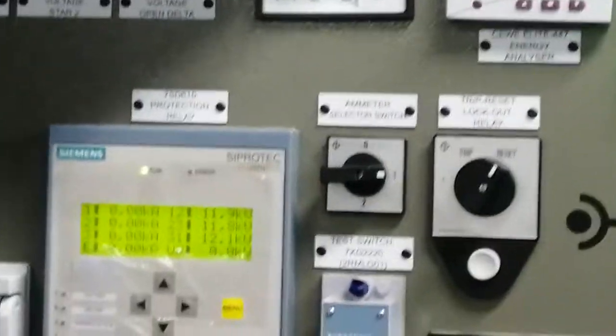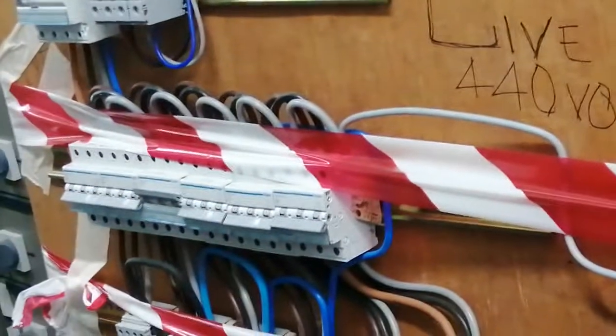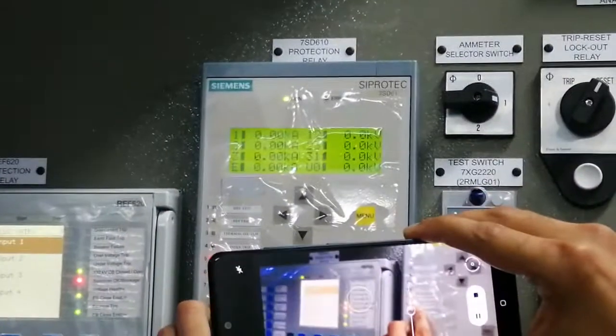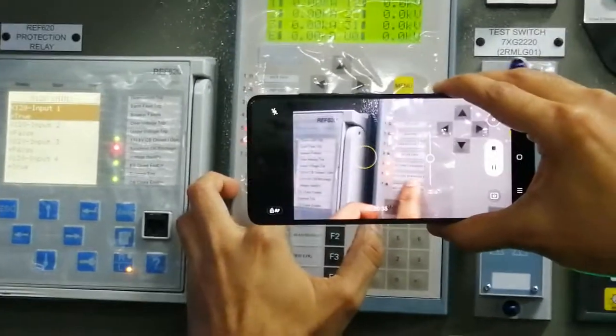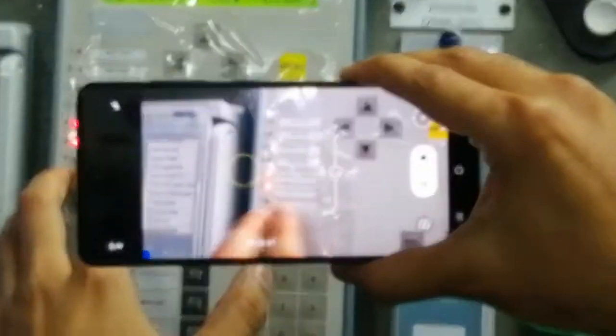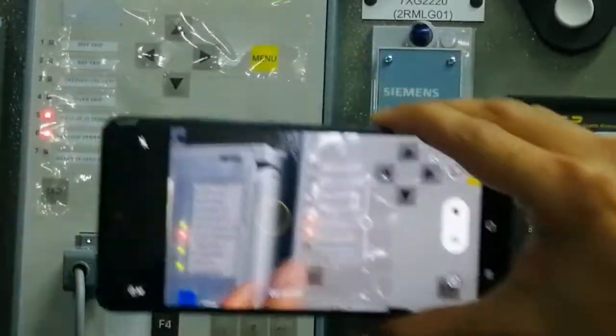So first I need to clear that. So I will switch off the line voltage. Now there is no voltage on this 11 kV panel line side, the cable side. Now I will check again. So still I have this earth switch close permission. This is the 11 kV SIPROTEC relay, and I have this permission from the 132 kV side to operate the earth switch in this panel.